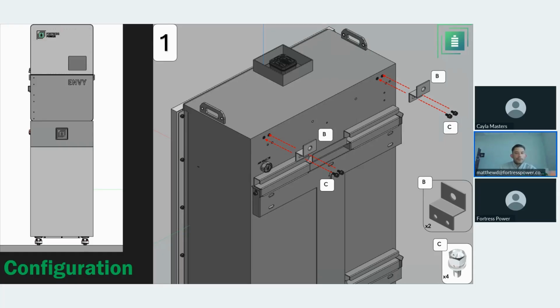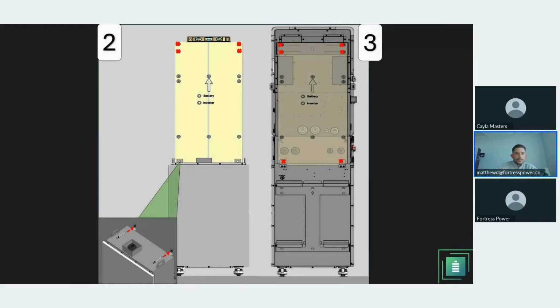So to comply with this configuration, where you have the battery and the inverter stacked on top, you start by installing the S-shaped bracket with these 4 screws against the back of the battery. Then you line the battery against the wall and put the template on top of the S-shaped bracket. Make your holes, so holes in the wall to fixate the battery, and holes for the ENVY inverter. This template will let you know the orientation. If it's a 12K, it's gonna show the marks you have to make for the 12K, or the 8K and 10K for the 8K and 10K.